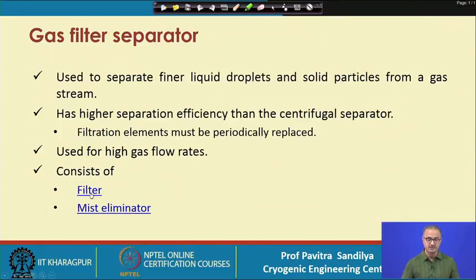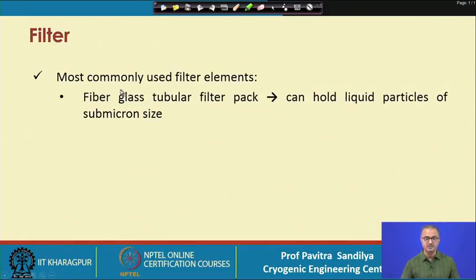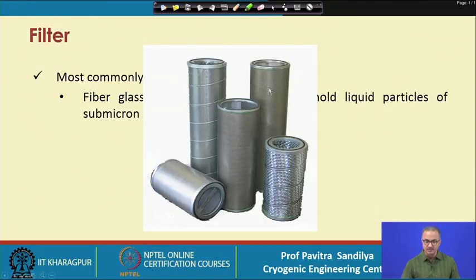The gas filter separator has two parts: the filter and the mist eliminator. The filters are fiberglass tubular filter packs which can hold liquid particles of sub-micron size. These typical filters have pores in them through which gas can pass, but the pores stop sub-micron liquid particles from passing through, so they will not be going out into the gaseous stream.